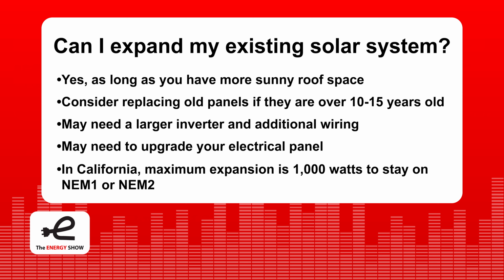If you're putting in a new inverter with more capacity, you may need to upgrade your electrical panel, downsize your main breaker, or install something called a power control system - we'll talk about that more later. There's always ways to do it. You can sometimes add a few more panels, sometimes more, but watch out for compatibility issues and work with installers who know how to do it. Otherwise, somebody throws a price at you, you sign a contract, and then when the engineering's done or you pull an electrical permit, it turns out the inspectors won't allow that change.